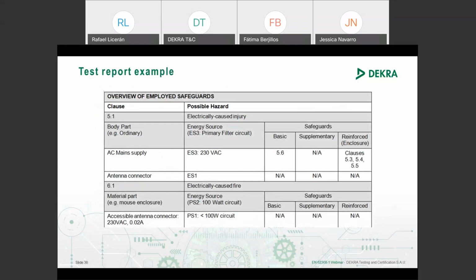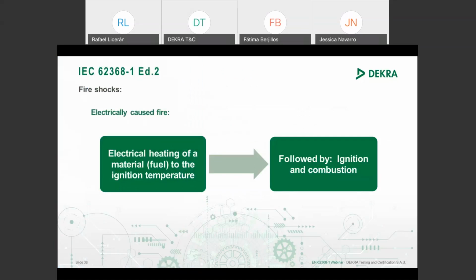Here you have another example of the test report in which you have to check this. To analyze the safeguards, first of all we classify the circuits in the first column, on the left part. For example, AC mains supply is classified as ES3, and I need different safeguards: basic safeguard and reinforced safeguard. For example, in this sample device, the antenna connector is not dangerous, is classified as ES1, and no safeguard is necessary; it is not applicable.